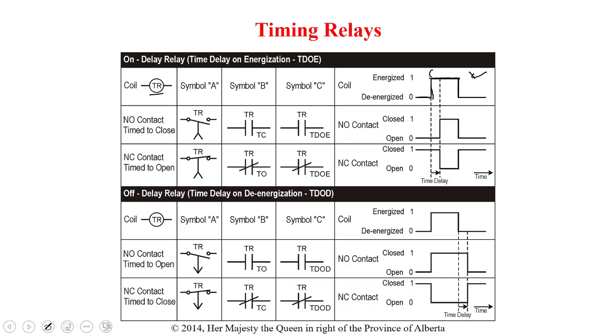So this little part right here is where the contacts, after this time has elapsed, will change state. As soon as coil power is removed, the contacts will go back to their normal position. So here we're going to look at some symbols for a normally open TDOE contact. When I see this symbol here, if I see the up arrow, that means on delay. All right, so it's an on delay timer, or time delay on energization.